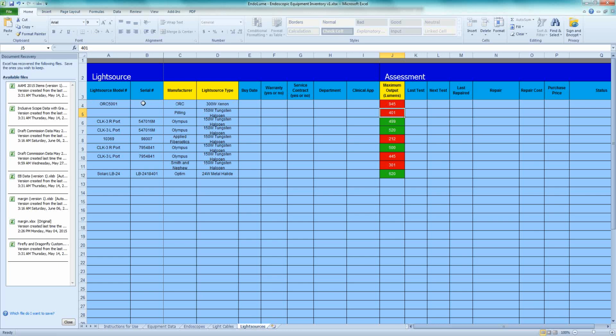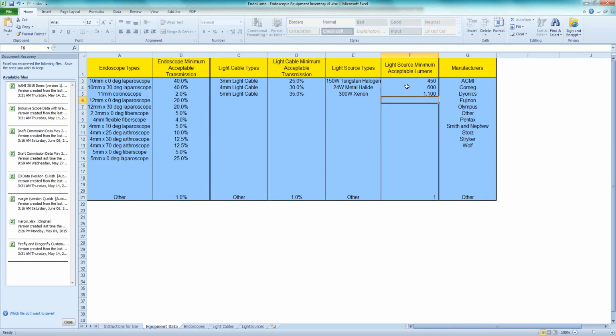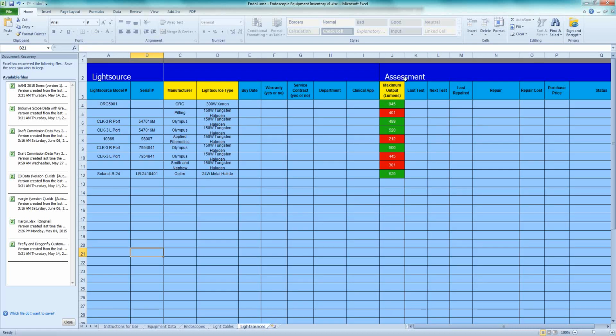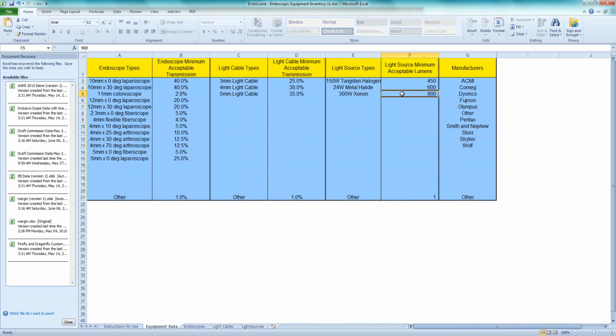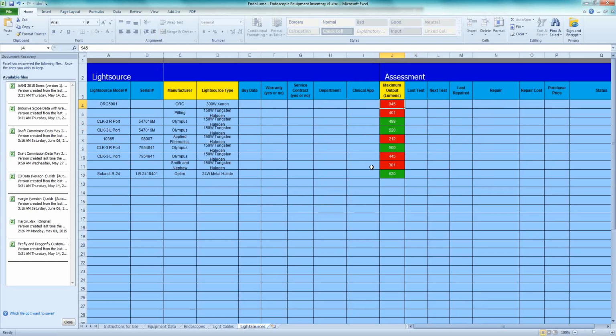So this lets the end user set these limits on one tab. Let's say I've decided that for my light source, I'm okay with 900 lumens being my minimum. I could go back and show, well, now it shows green again because that's what I changed it to. Or you can just use our default limits of 1100 lumens, and then when you go back, you see that the 945 lumens you measured shows that it does not meet specification.